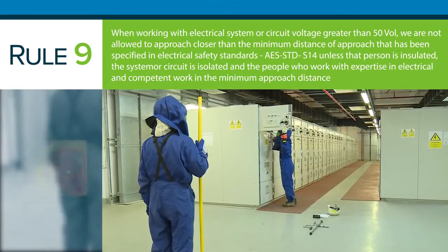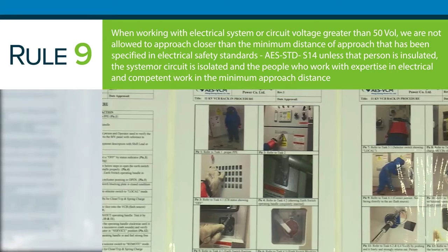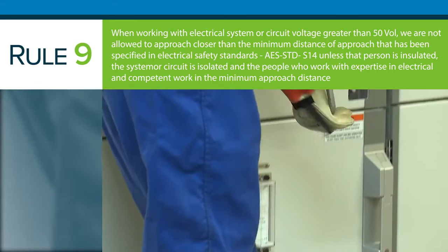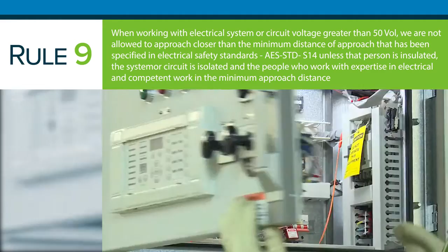When working with an electrical system or circuit with voltage greater than 50 volts, we are not allowed to approach closer than the minimum distance of approach specified in electrical safety standard AES STD S14, unless the person is insulated, the system or circuit is isolated, and the person working has expertise in electrical work and is competent within the minimum approach distance. Do not ever skip or ignore safety equipment.